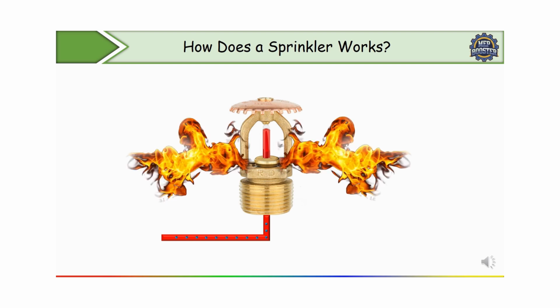When the air around the sprinkler reaches a certain threshold, what happens? The liquid inside the glass bulb expands and the bulb bursts. And finally, the sprinkler head, can you see here, disperses water in a specific pattern to cover the area below it. The pattern and coverage depend on the type of sprinkler head, which we'll discuss. Is it clear? So in this way the sprinkler works.